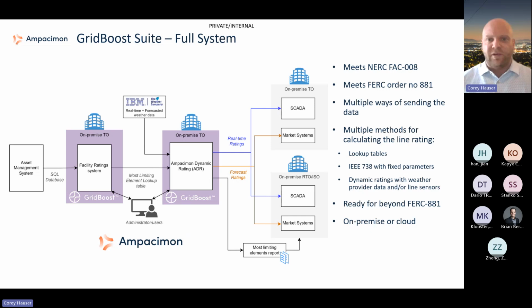We also have another customer who has chosen to use both systems together. They have the facility rating solution for the terminal equipment, which feeds into the ADR system and creates that most limiting element, as we saw. They also use our ADR and GridBoost Advanced system. There, while they don't have the same ramp up as the one we talked about before, they set certain temperature ranges for wind. They also noticed it gets a little windier as it warms up, so at a certain area they use a couple feet per second, then 3, then 4 feet per second wind at certain different temperature ranges.